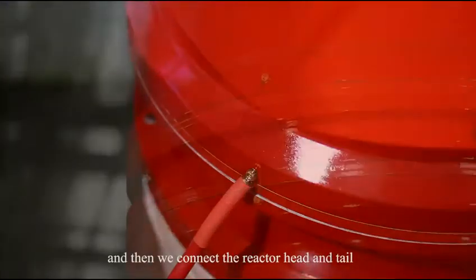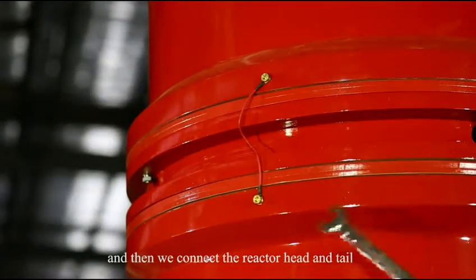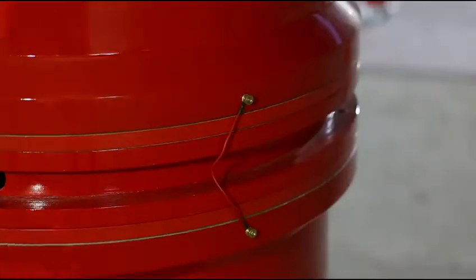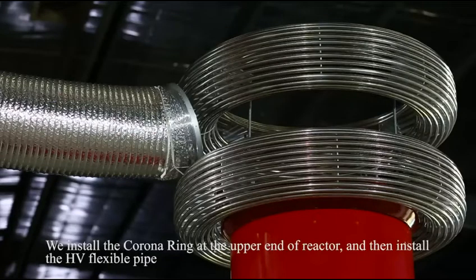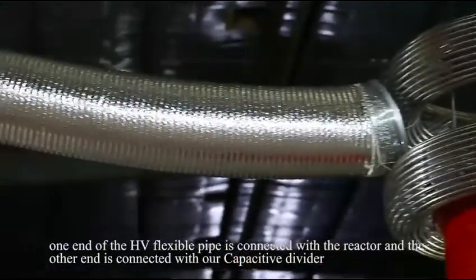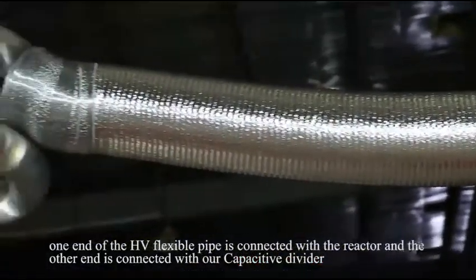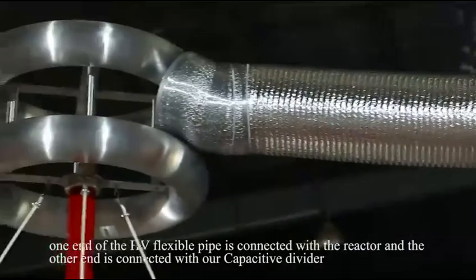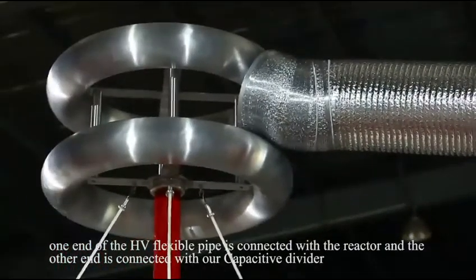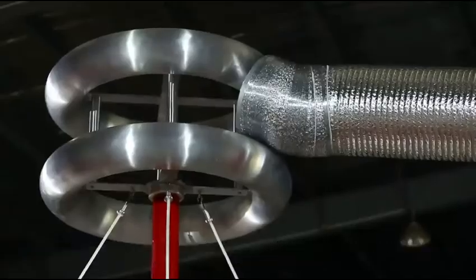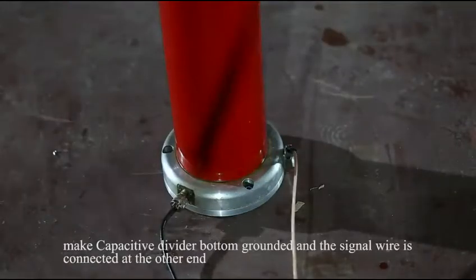And then we connect the reactor head and tail. We install the corona ring at the upper end of the reactor, and then install the HV flexible pipe. One end of the HV flexible pipe is connected with the reactor, and the other end is connected with our capacitive divider. Make the capacitive divider bottom grounded, and the signal wire is connected at the other end.